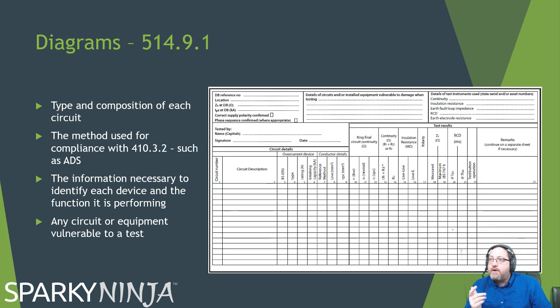You also need to be aware of the diagram requirement. So 514.9.1 tells you that you need to have labeling and a diagram that gives you the type and composition of a circuit, the equipment sensitive or vulnerable to typical tests, the method for compliance with 410.3.2, so ADS if that's your protective measure. All that needs to be documented, and labeling needs to be applied with that information on it for future designers. Make sure it's there.